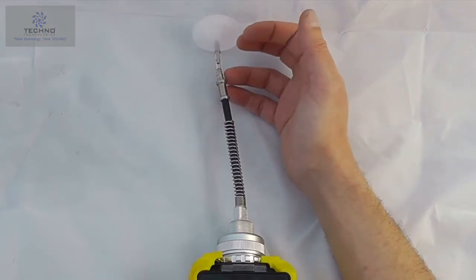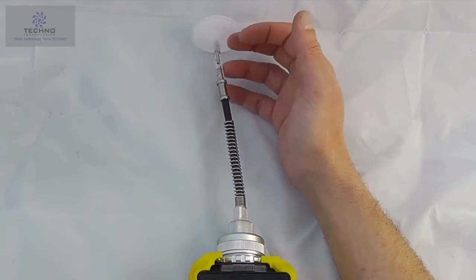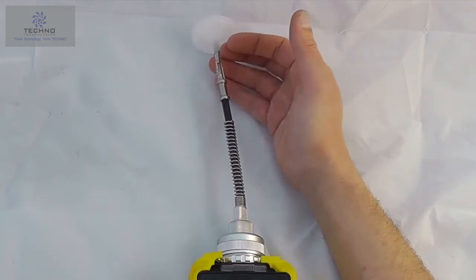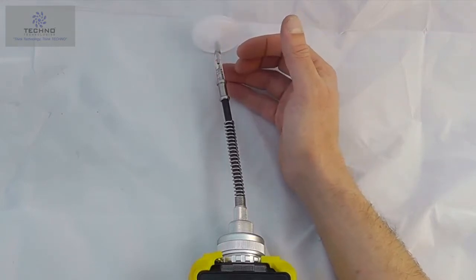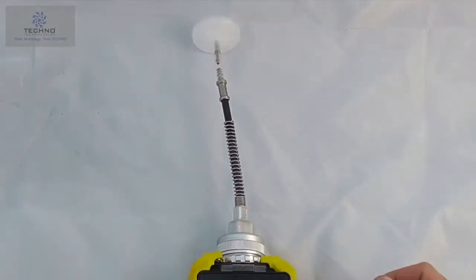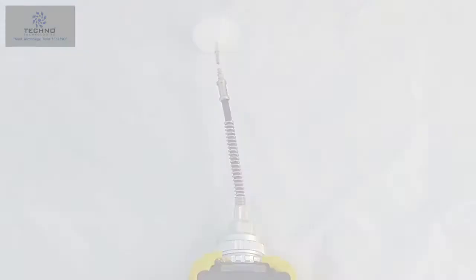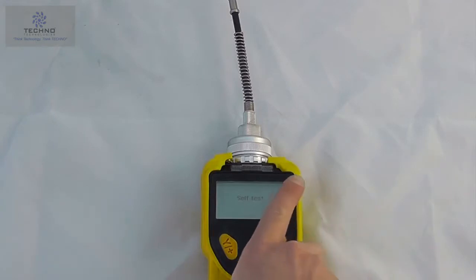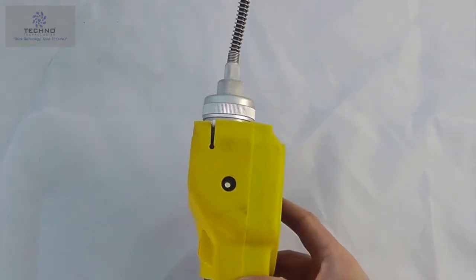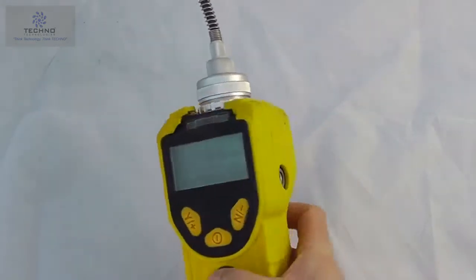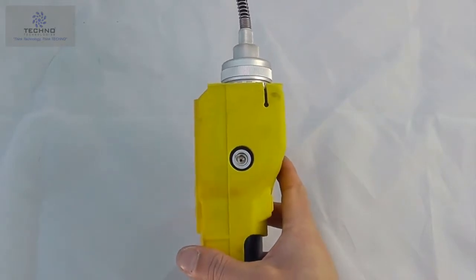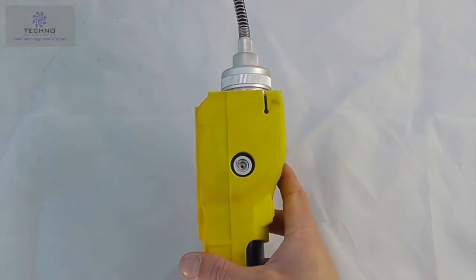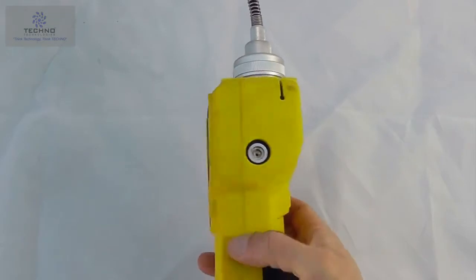Also always check this tubing section to make sure there's no contamination in that section of the line. It can act like a sponge for VOCs. The important things to identify externally are the sounder on the left hand side of the instrument and the exhaust port on the right hand side of the instrument.